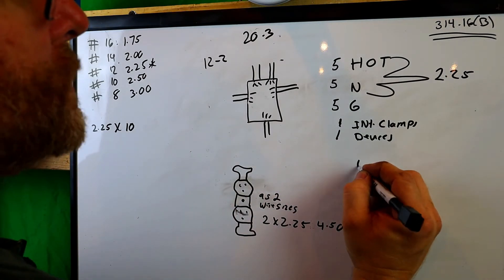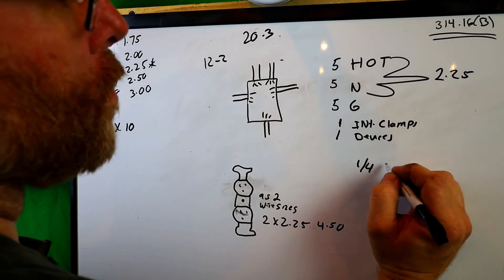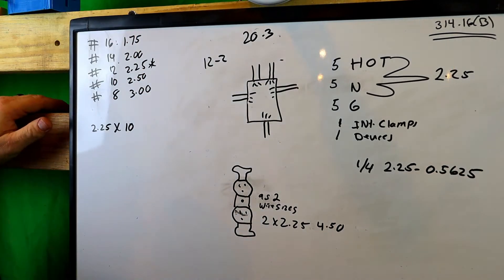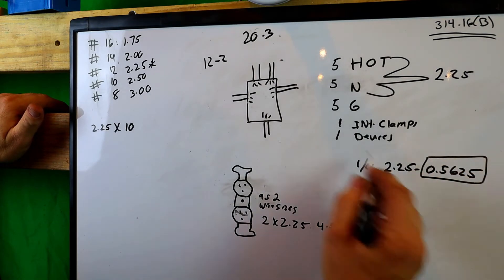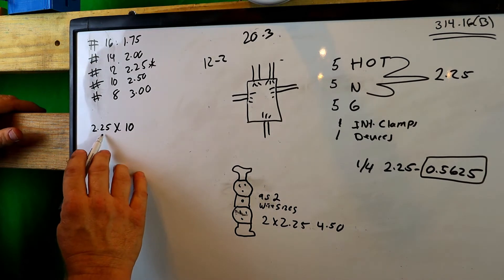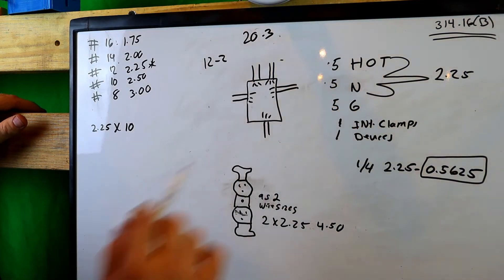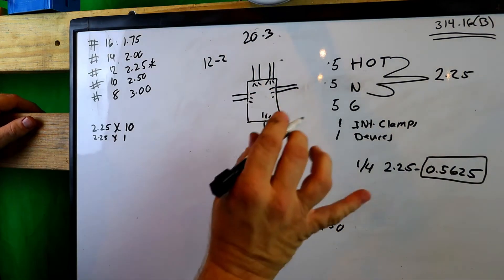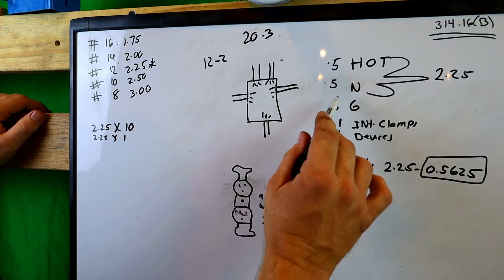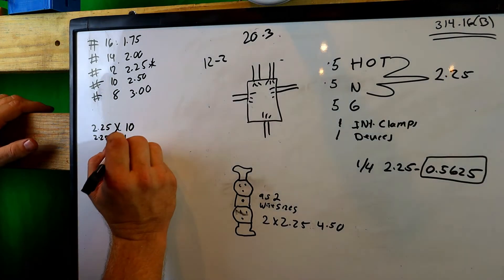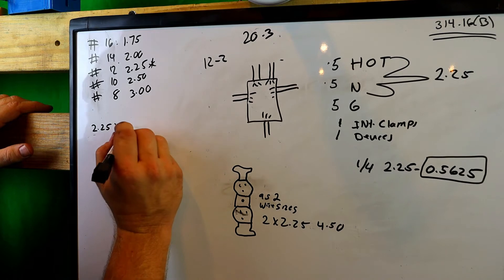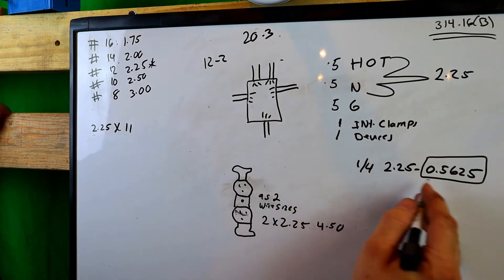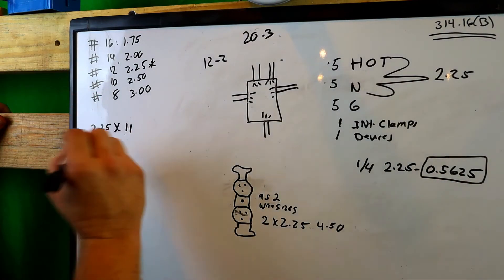This is what the fifth wire will be counted as. We have 2.25 times 10 - that's these two wires right here, the hots and neutrals. We also have to add one more 2.25 times one for our ground. Now I know this is going to be confusing but you gotta listen to me. You have five grounds - four of them are going to be treated as one size wire, so we'll put this as right here. Now we're at 11 times 2.25 - there's 10 hots and neutrals, and one ground at 2.25. The other one will be treated as 0.5625.